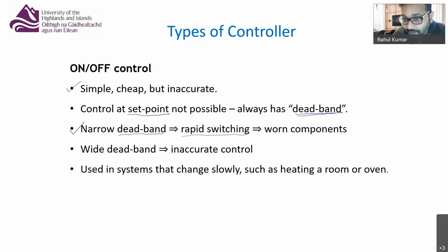And as a result of that, it will wear your components or it will damage your components. Okay. Now again, you can increase the dead band, you can have a wide dead band, but that will obviously be an inaccurate controller, or it will increase your inaccuracy, right?